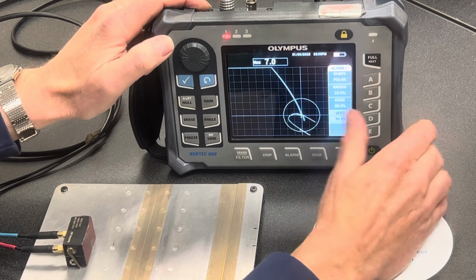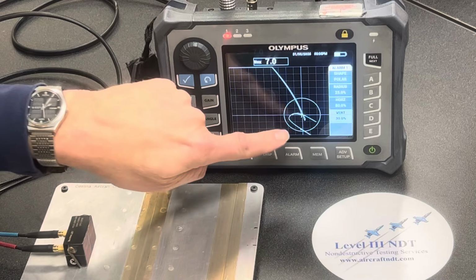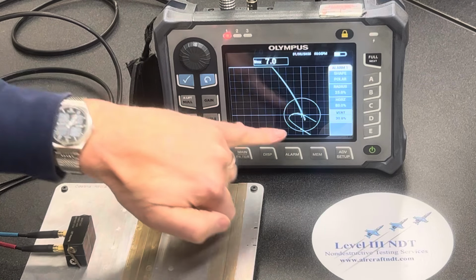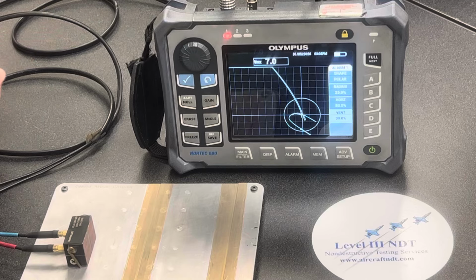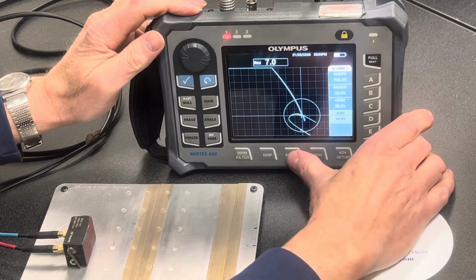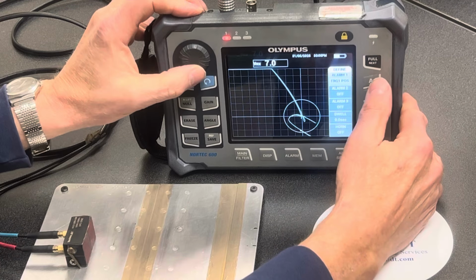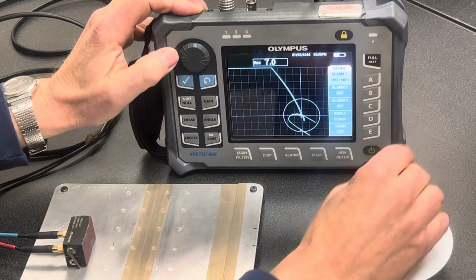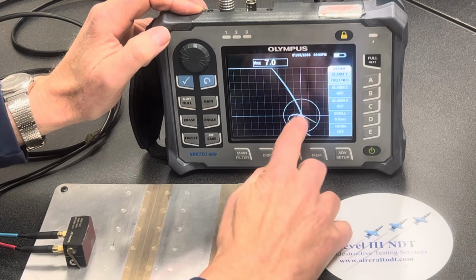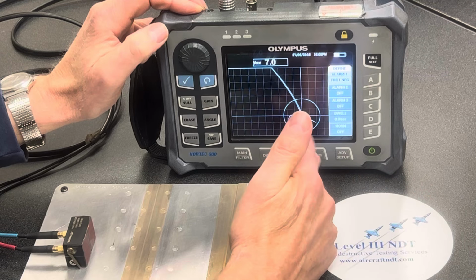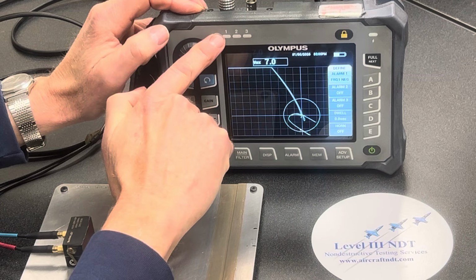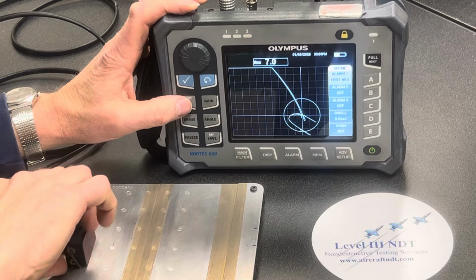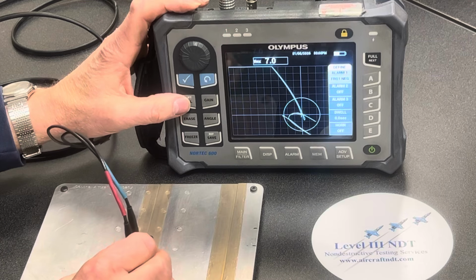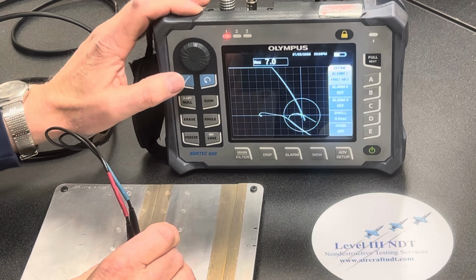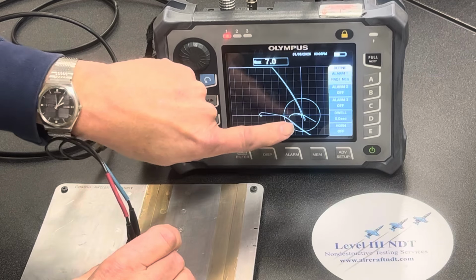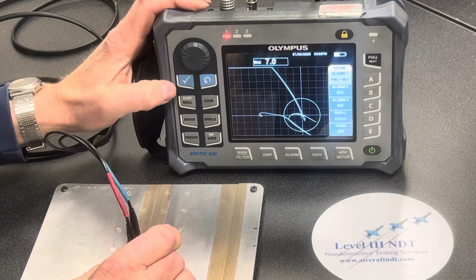You'll notice that when the alarm encompassed the point of the impedance plane dot on the screen, we got the alarm. So we're going to go ahead and change the logic of the alarm from positive to negative. So now, as long as the dot's inside the alarm quadrant, we don't get a visual alarm on the instrument. We'll go back to our calibration standard. You'll see that we're outside of the polar alarm now, so we have an alarm indication.